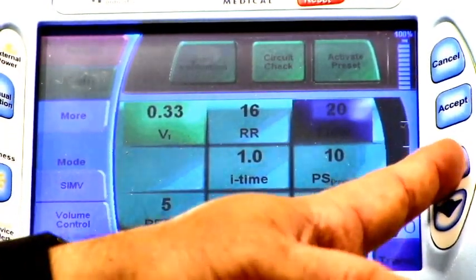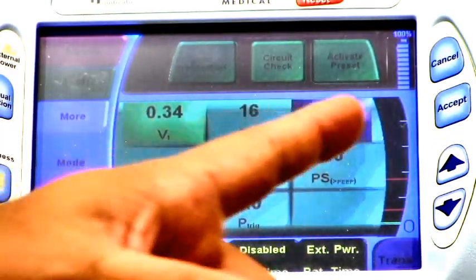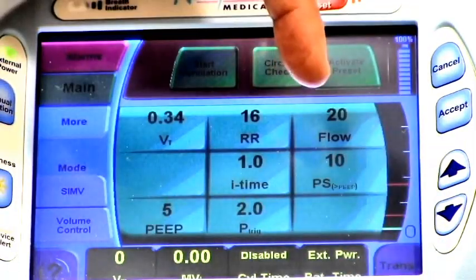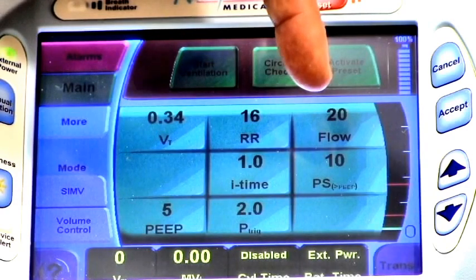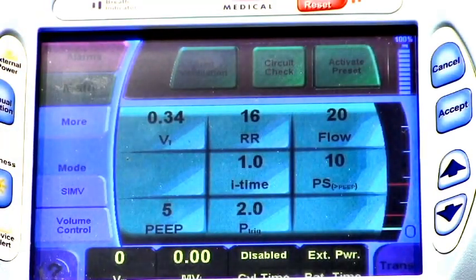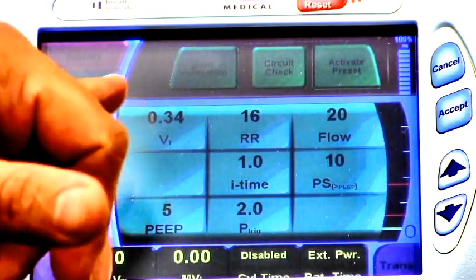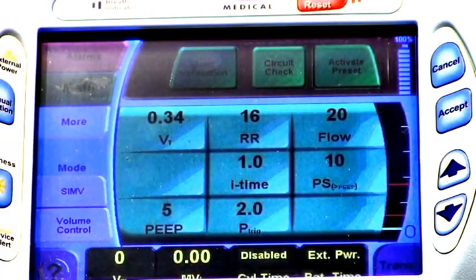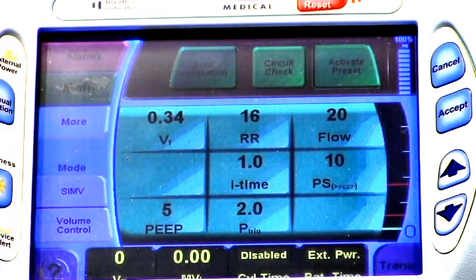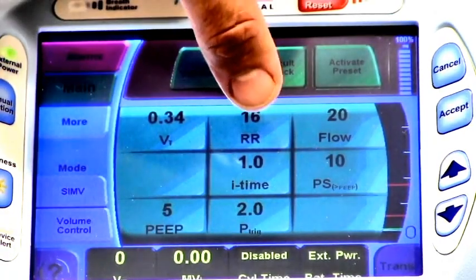And I'm just going to set it for 340 cc's of air. Remember, when we're done, we hit accept. It will default back to that natural green that was with the rest of the pieces. And so that's where we want it to be. If you do not hit accept, that will default back to where it was before, which I believe was 290 cc's of air. The next thing we're going to set is our respiratory rate.